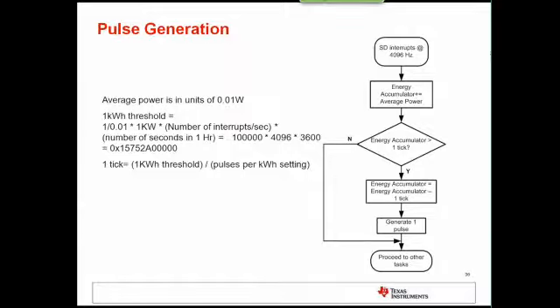For pulse generation, in the actual active power register, 1 kilowatt hour threshold is defined as this number, and based off this number, a tick is calculated. The tick is calculated based off of a pulses per kilowatt hour setting that's set in the software. Whenever you accumulate energy, you accumulate the calculated energy from the previous frame. Once the energy accumulator has enough energy that corresponds to 1 tick, then 1 pulse is generated, and the energy accumulator is decremented by the amount that corresponds to 1 pulse.